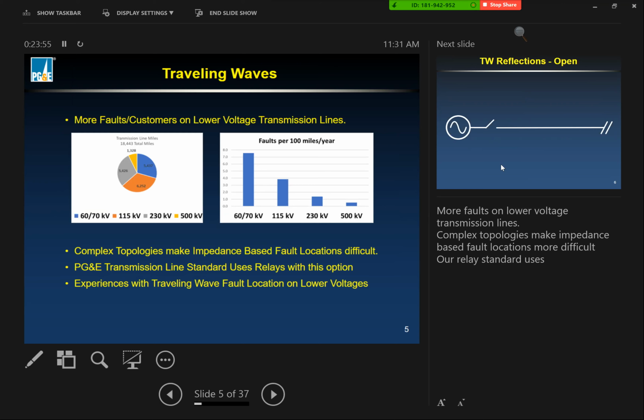Part of the reason we were able to do this is we changed our protection standard, and it sounds like from our discussions with the SMUD guys this morning, that they're changing the same relay that we're using, which is a 411L relay model, that as an option you can enable traveling wave in that relay. So we're not having to buy a whole new relay to do this. All we have to do is enable that option, pay a little extra, and we have traveling wave relays already installed.